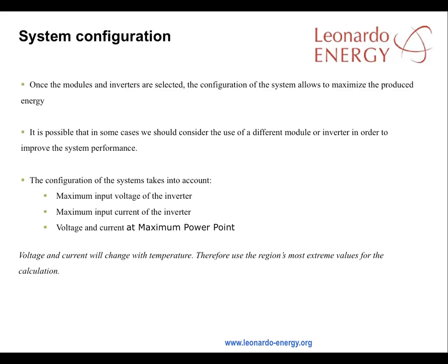Once the modules and inverters are selected, the configuration of the system should allow maximization of produced energy. In some cases, a range of modules and inverters should be considered in order to find the combination that offers the best system performance. The configuration should take account of the maximum input voltage and current of the inverter, and the voltage and current at maximum power point. When designing the solar panel configuration in series and parallels, take account of the fact that voltage and current will change as the temperature changes, so it will be necessary to choose the most extreme values possible in the region when making the calculation.